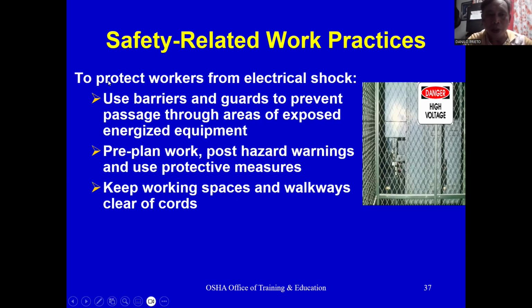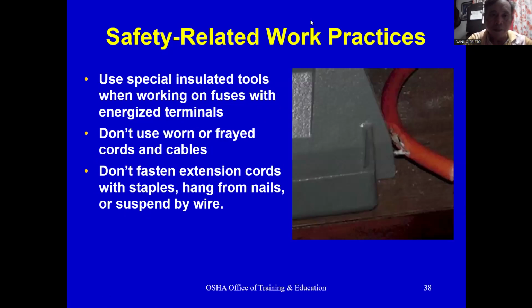Next, safety-related work practices. To protect workers from electrical shock, use barriers and guards to prevent passage through areas of exposed energized equipment. Pre-plan work, post hazard warnings, and use protective measures. Keep working spaces and walkways clear of cords, as shown in the picture. Use special insulated tools when working on fuses with energized terminals. Don't use worn or frayed cords and cables. Don't fasten extension cords with staples, hang them from nails, or suspend them by wire.